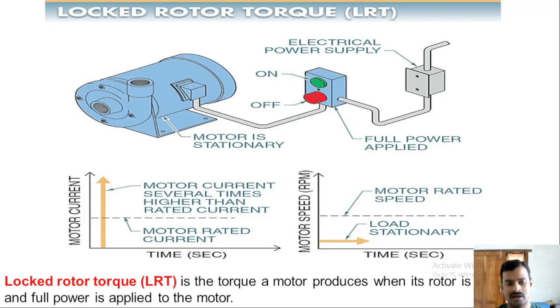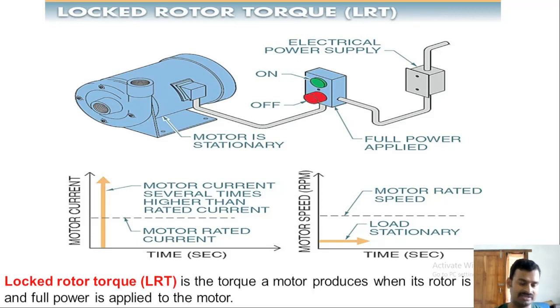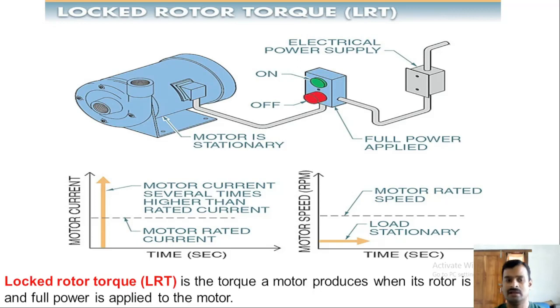The difference between locked rotor current and starting inrush current is important. Locked rotor torque and locked rotor current refer specifically to when full supply voltage is given directly to the motor. If voltage is reduced by any starting method — such as star-delta, auto-transformer, or primary resistance starting — then the current and torque during starting are called starting current and starting torque, not locked rotor current or torque.